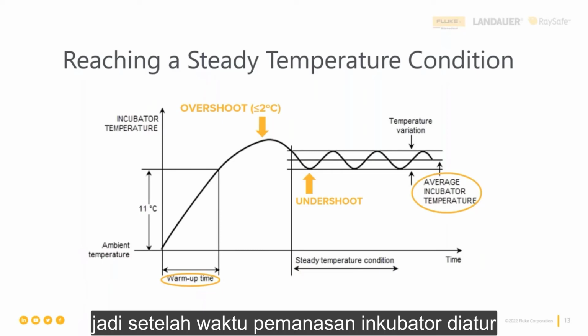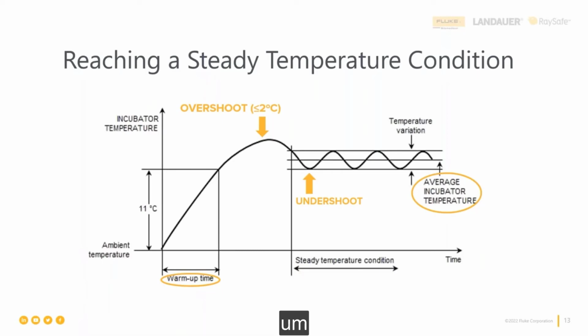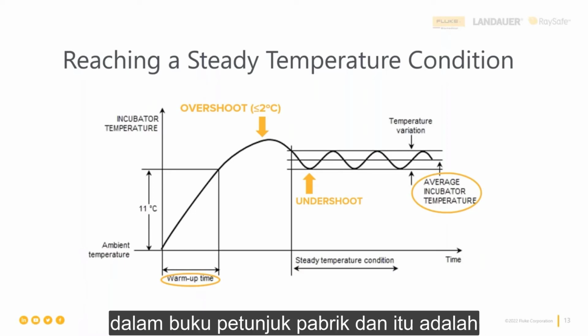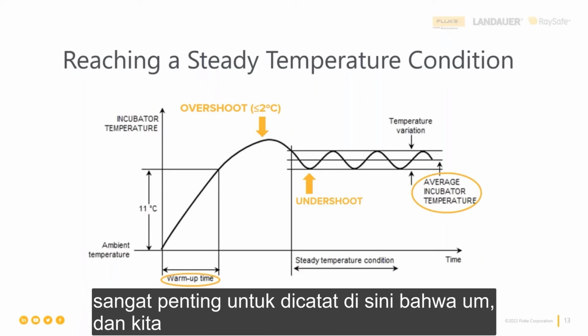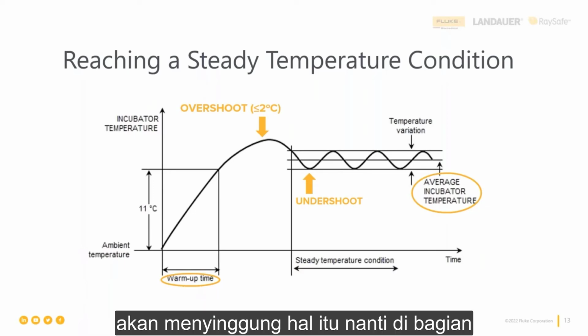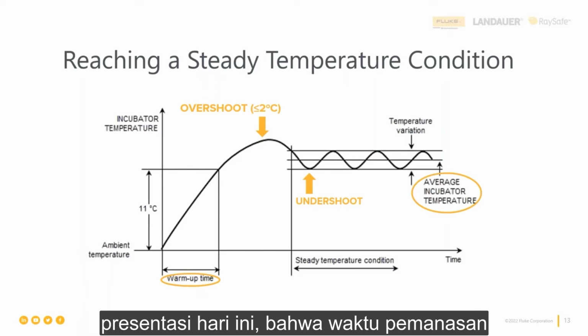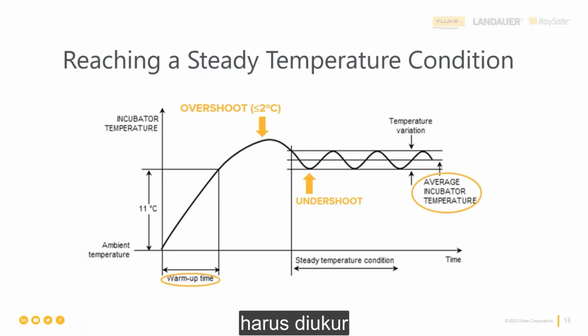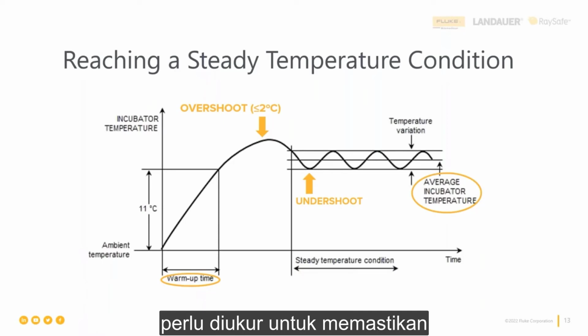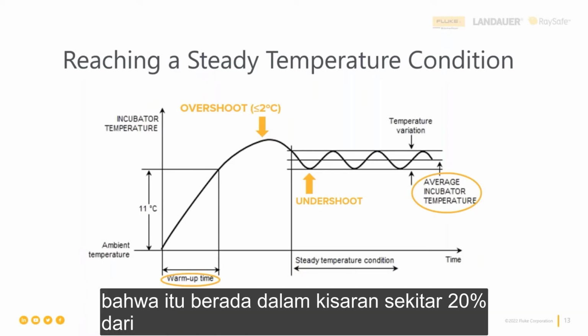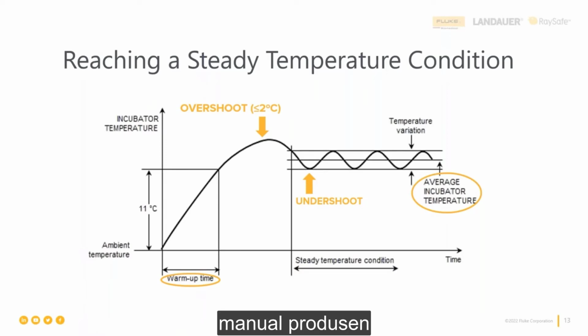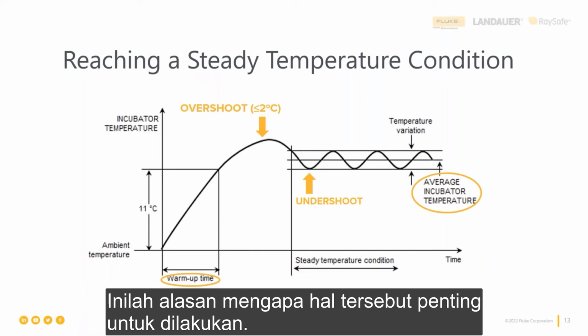Once an incubator warm-up time is set, and by the way, the warm-up time is set in the manufacturer's manual, it is very important to note, and we will touch on that later in the presentation today, that the warm-up time must be measured. It needs to be measured to make sure that it is within about 20% range of the time that is listed in the manufacturer's manual. And here is why it is important to do that.